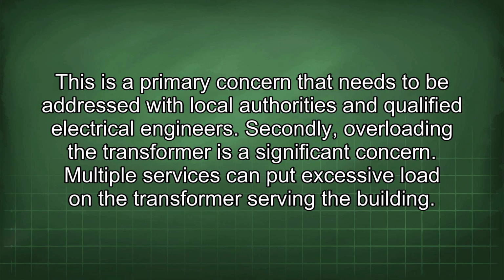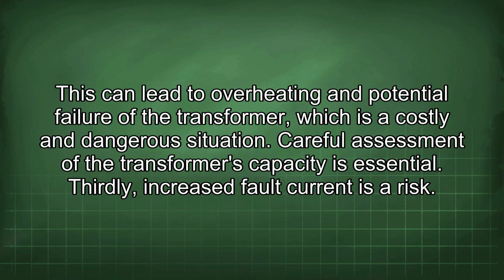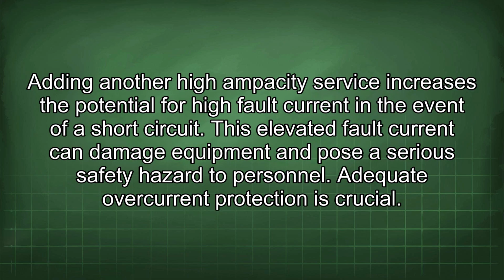Secondly, overloading the transformer is a significant concern. Multiple services can put excessive load on the transformer serving the building. This can lead to overheating and potential failure of the transformer, which is a costly and dangerous situation. Careful assessment of the transformer's capacity is essential. Thirdly, increased fault current is a risk. Adding another high-ampacity service increases the potential for high fault current in the event of a short circuit. This elevated fault current can damage equipment and pose a serious safety hazard to personnel. Adequate overcurrent protection is crucial.